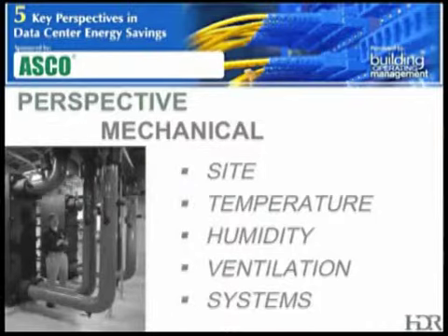Then we've seen applications where we're moving into the rooftop air handling units, again with airside economizers, sometimes with a form of either direct or indirect evaporative coolers, and of course probably for most climates some form of mechanical cooling, either chilled water or DX, to handle the extremes. And then for maybe large-scale facilities, you can start to consider central chilled water plants. I'd say this is more of a rarity unless you really had something on a very, very large scale.